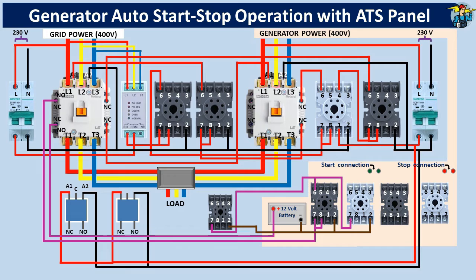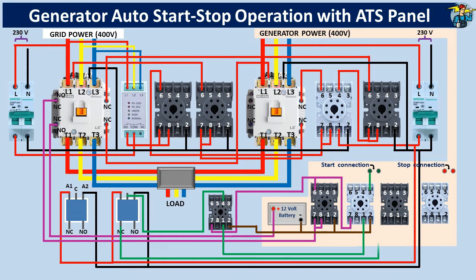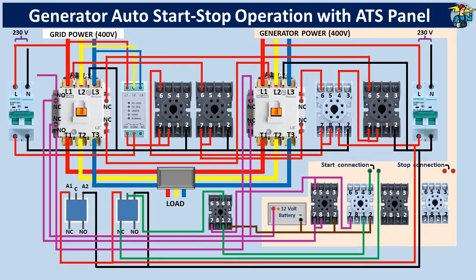The generator starting point connection line passes through 3 relays — through points 1 and 3 of the starter relay, points 1 and 4 of the start failure detection relay, and through the common and normally closed points of the SPDT relay that operates through the generator run signal. To stop the generator, take the line from the positive end of the battery and pass it through the normally closed auxiliary contact points of the generator contactor. This line must also pass through the normally open auxiliary contact points of the mains contactor before connecting to port number 7 of the generator stop timer.